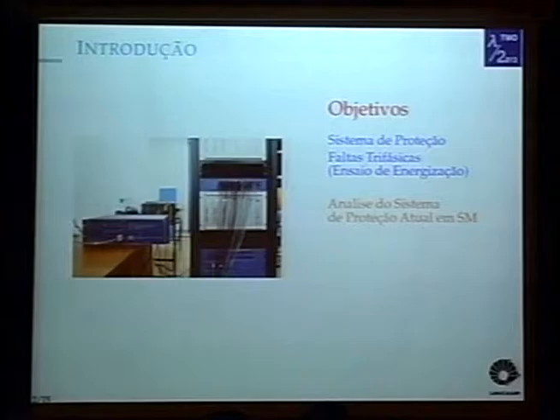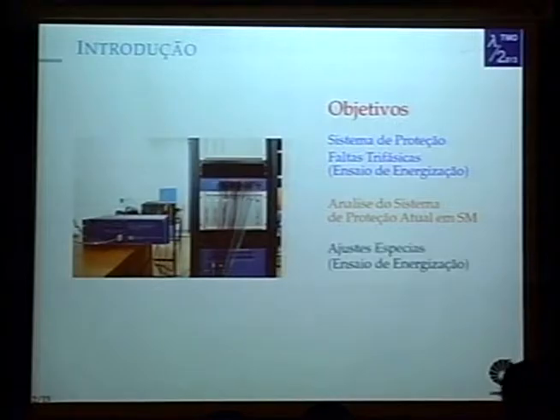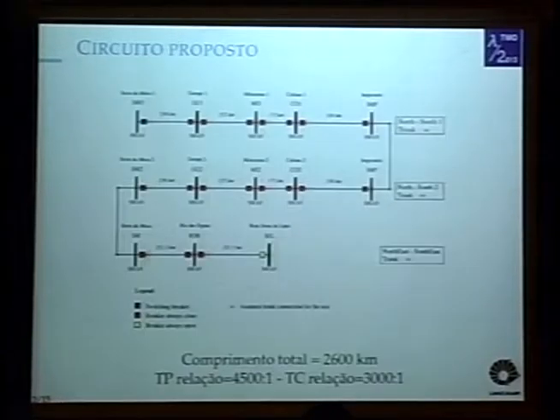So we need to analyze if its adjustments are enough, if the hardware available is enough. And after that, we need to study some special adjustments, change the conventional philosophy we have, which is the protection to long distance, so we can have a better performance in the protection system for the energization study when we have 3-phase faults.